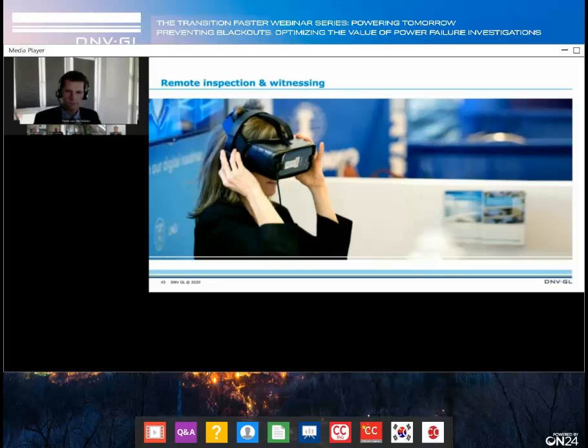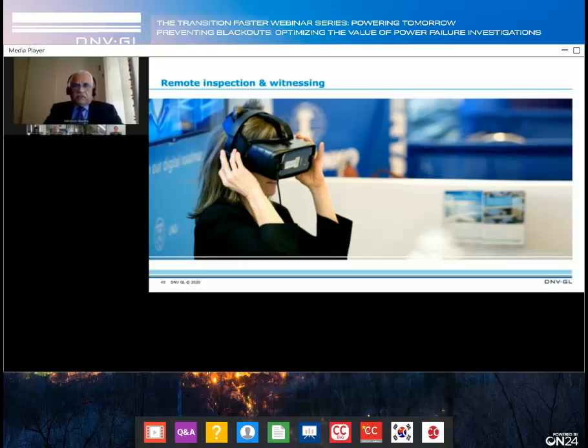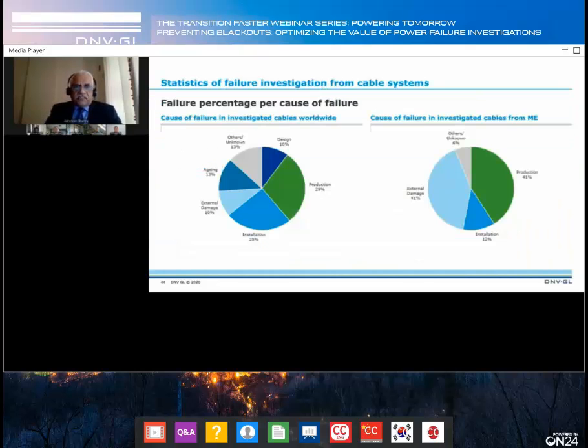Yes, Peter, indeed. The presentation is being done in the GCC CIGRE event, which is going in parallel with our webinar. So I would like to talk about the cable systems. As you presented before, the different phases of the asset life cycle, here our comparison of the global numbers to the statistics of the Middle East is presented on the asset life cycle phase of the cable system. Here you can notably see that from design till the aging part there are different numbers, but in the Middle East, the key contribution of the failure is coming from the installation, the external damage and the production.